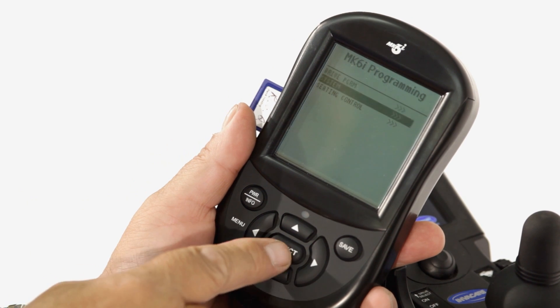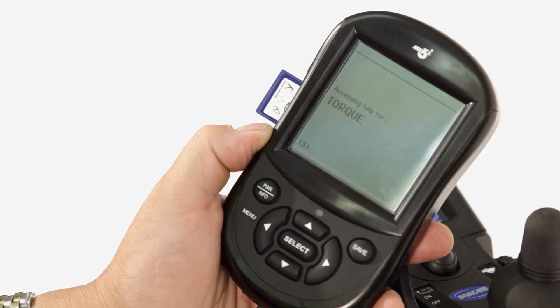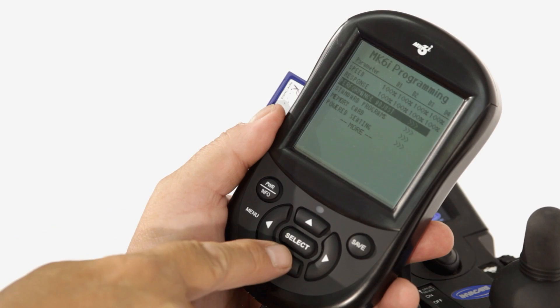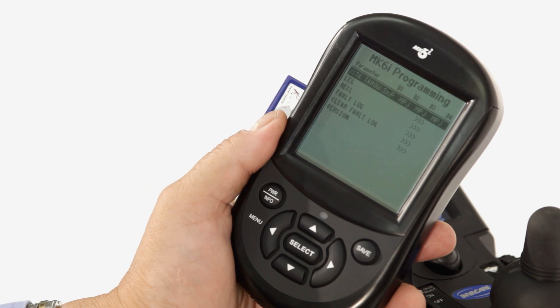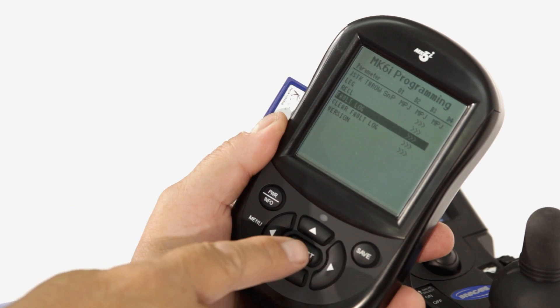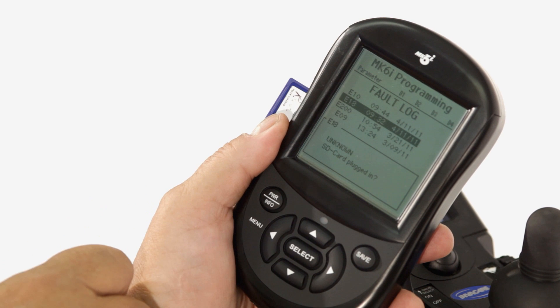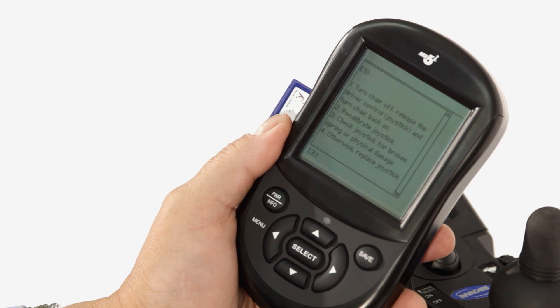Use of the SD card adds a level of programming expertise for the technician, the RTS, or the clinician. They can be used with the programmer to look at programming definitions or even identify the steps needed to resolve a particular error code. Diagnostics are easy with Mark VI Electronics, with several options available. The handheld programmer holds a list of diagnostic tools in the menu. With a professional SD card, you will not only be able to see the definition of all fault codes, but by pressing the help key be able to see, step by step, how to resolve the fault.